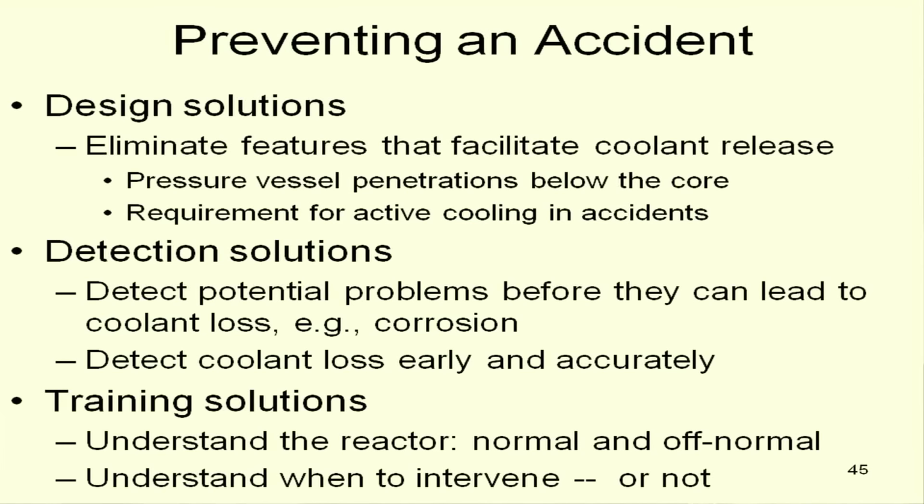But now, preventing an accident. You want to eliminate features that facilitate coolant release. You'd like not to have pressure penetrations in the pressure vessel low, below the core, because if one of those breaches, no matter how much water you keep pouring in the top, if you've got a hole in the bottom of your bucket, you're in difficulty already.